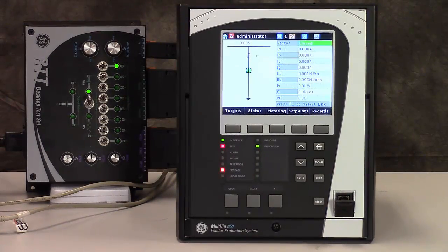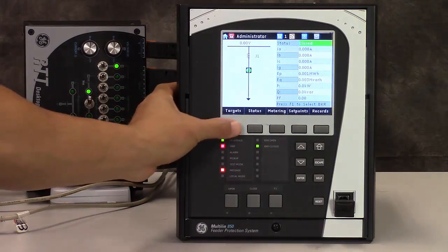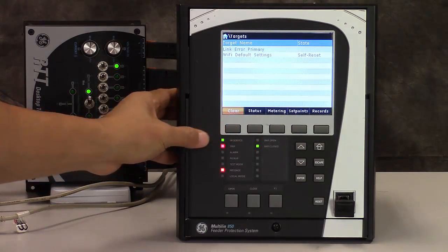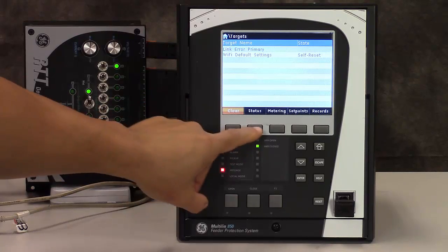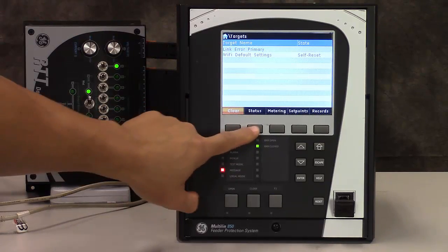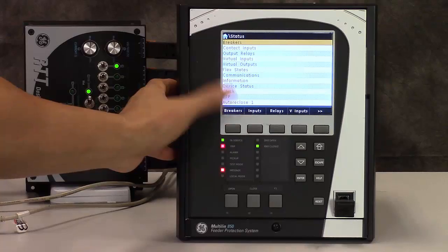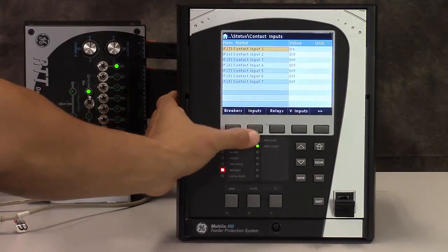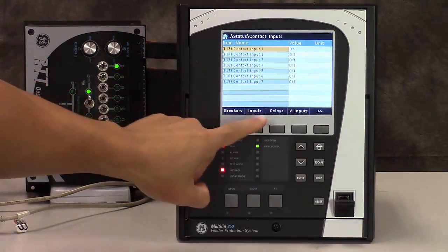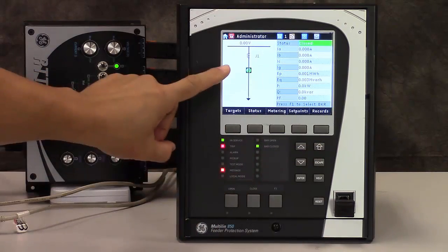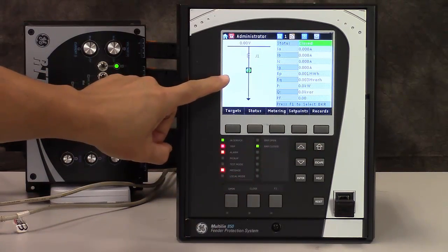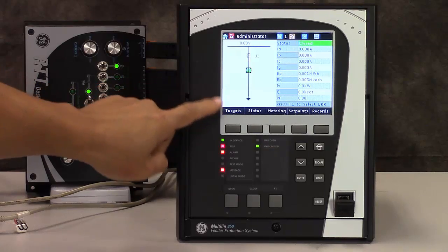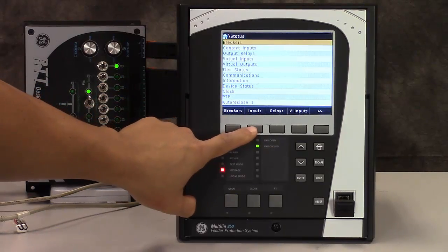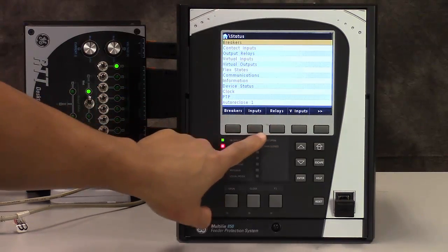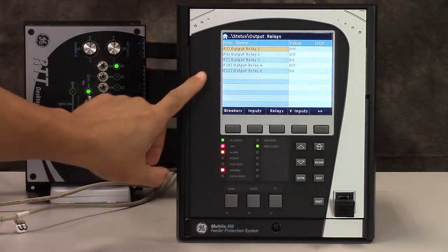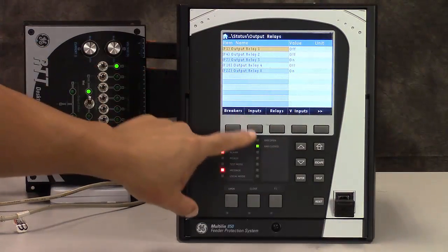From the front panel of the 850 relay, we can also check the target message, which element has operated. We can also check the status of the breaker and the contact information. For example, for the contact inputs, we see contact input 1 is on. That's configured as the 52A, the circuit breaker. And we can also check other information, for example, the output relays. In this case, we've got relay 3 operated.